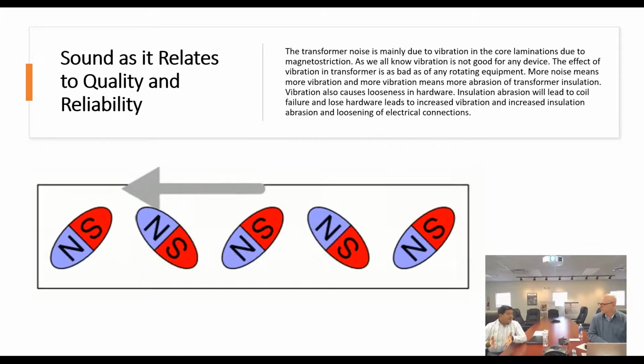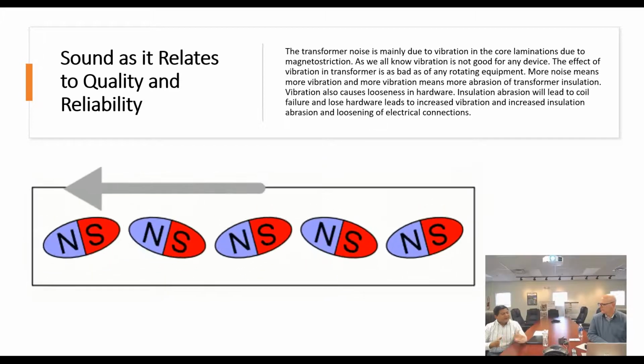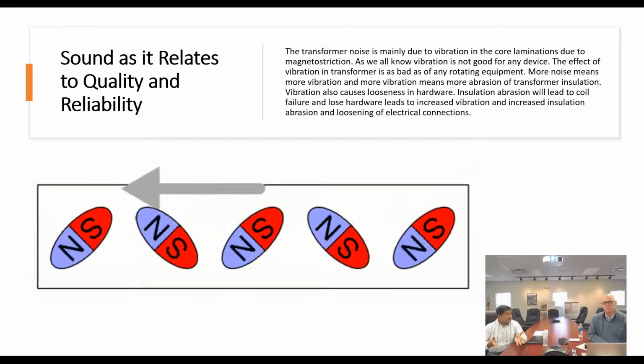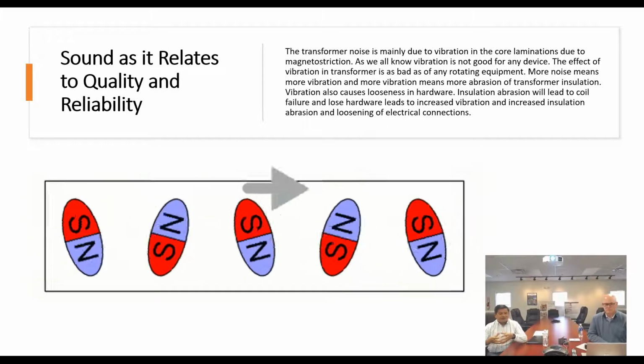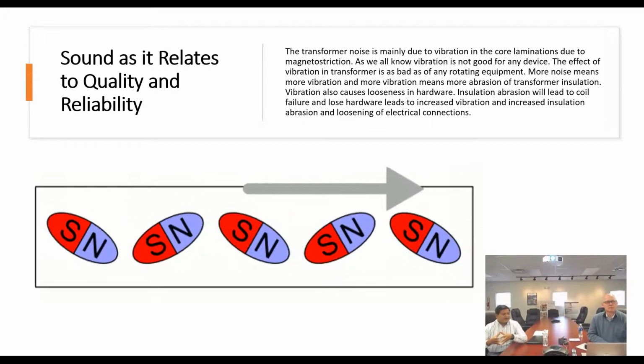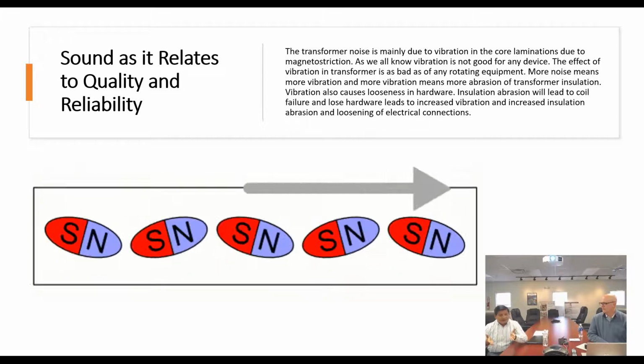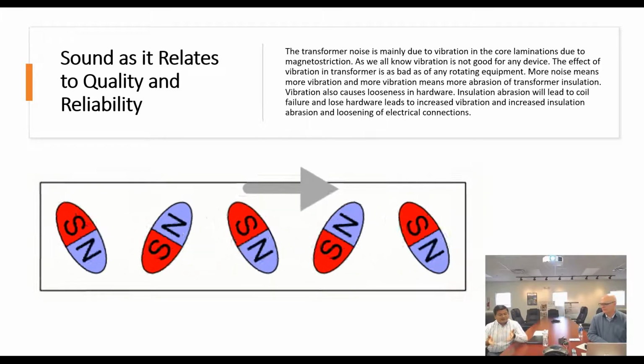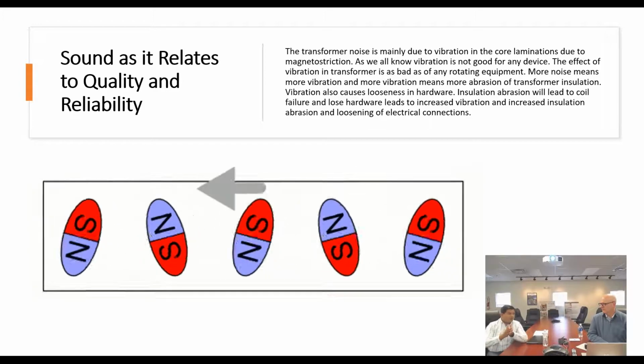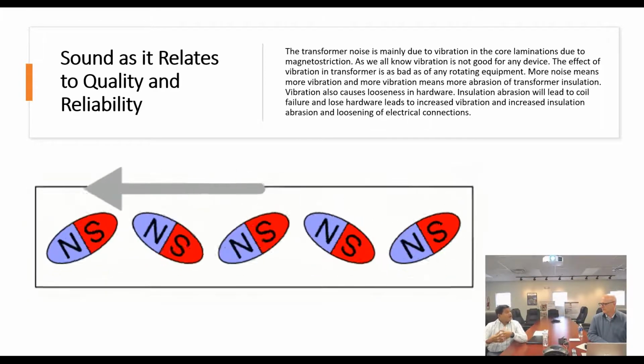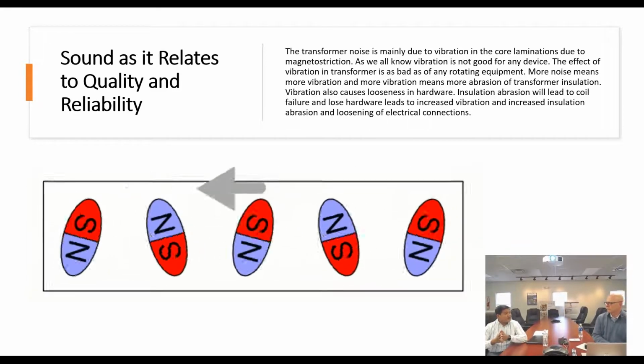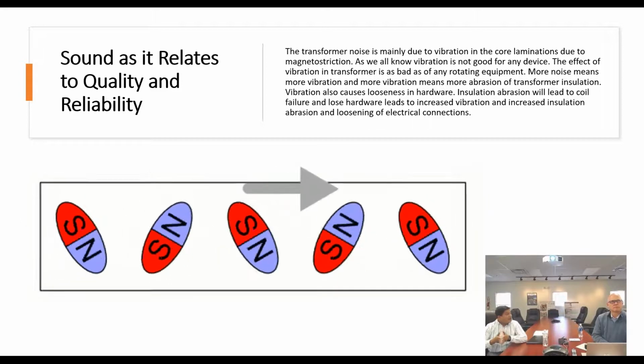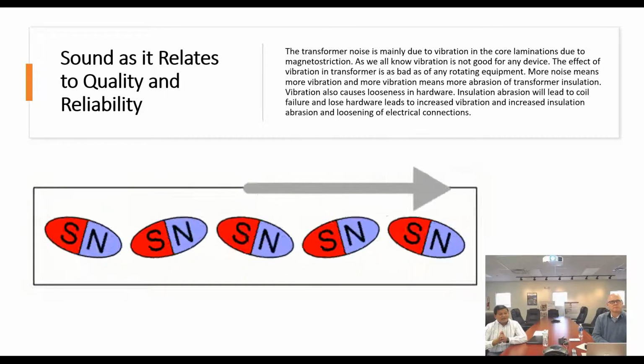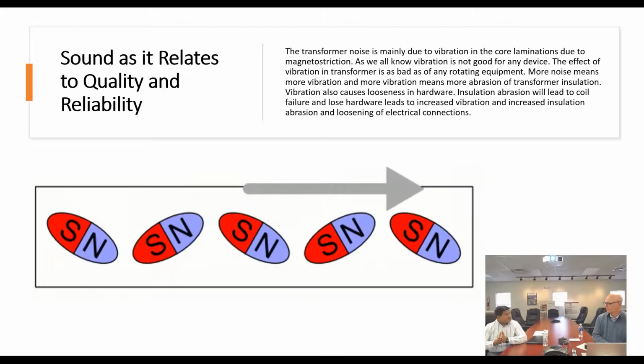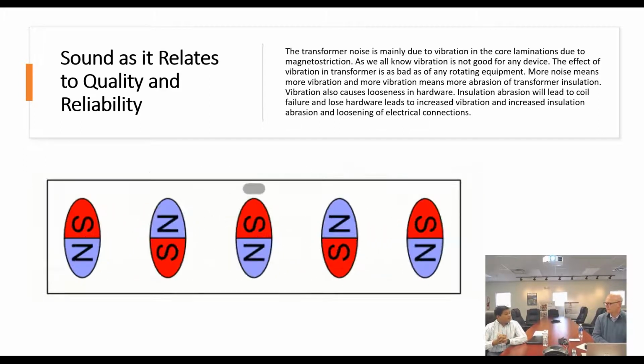So, the quality and reliability of the transformer. Let me put it in a simpler way to understand. When transformer noise is generated, it is generated because of vibration, due to the magnetostriction effect, the vibration of the core and the vibration of the winding, all coming together. Now, if there is more vibration, the winding insulation starts rubbing against each other. That's abrasion of the winding insulation.